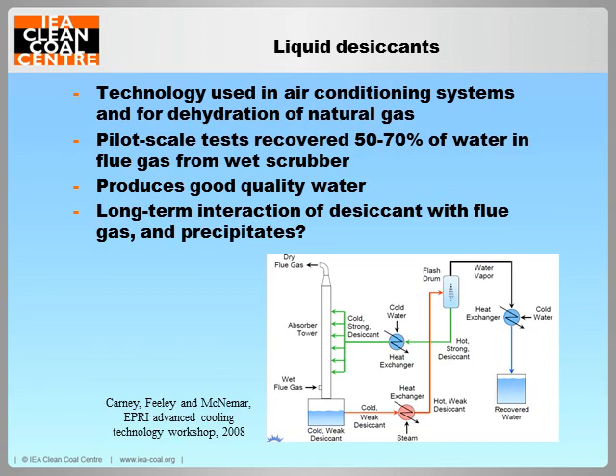A liquid desiccant-based process has been developed and tested at pilot scale by the University of North Dakota's Energy and Environmental Research Center in the USA. Some 50 to 70% of the water in the flue gas from a wet scrubber was recovered. Now, this technology is not new. It is already used in air conditioning systems in buildings, and for the dehydration of natural gas. It has not yet been demonstrated on a coal-fired power plant.